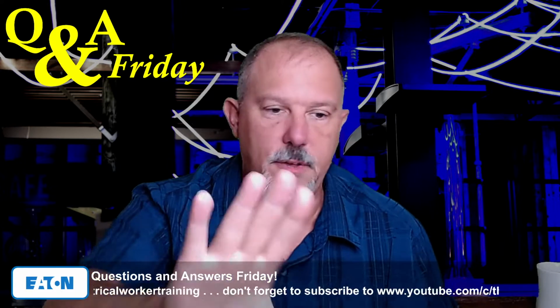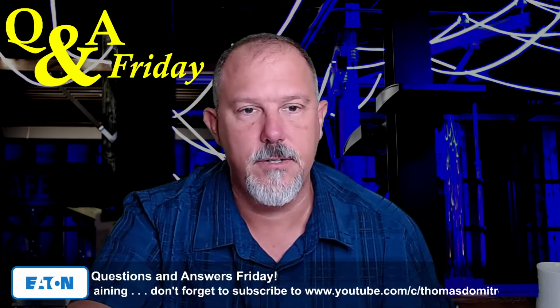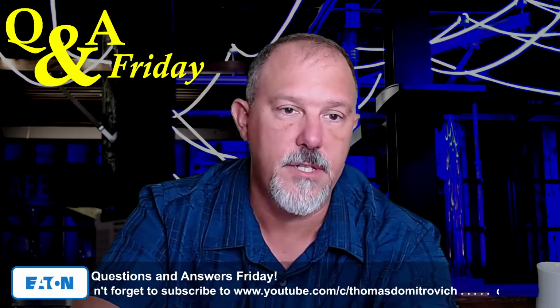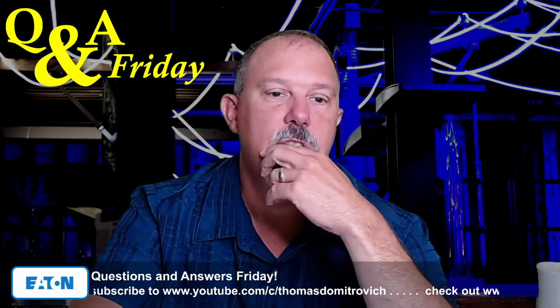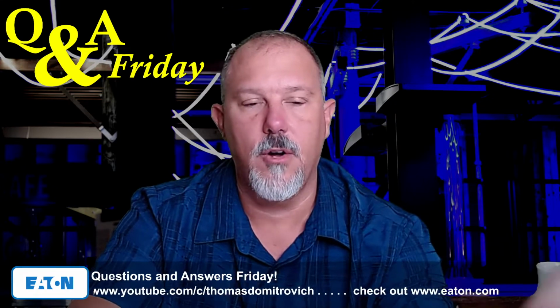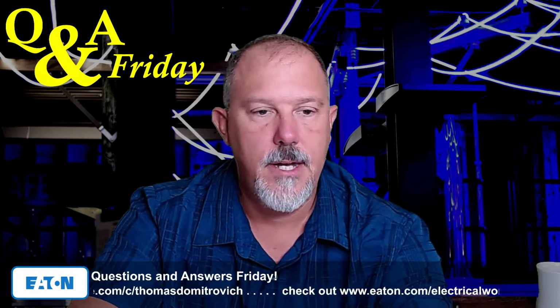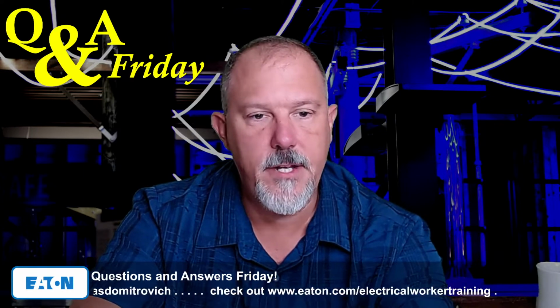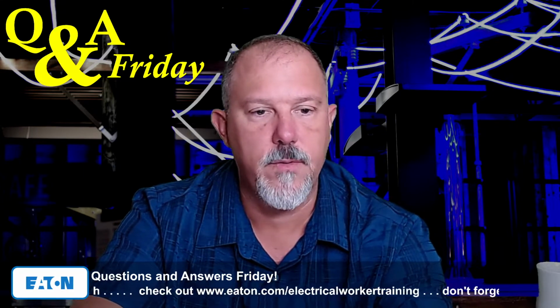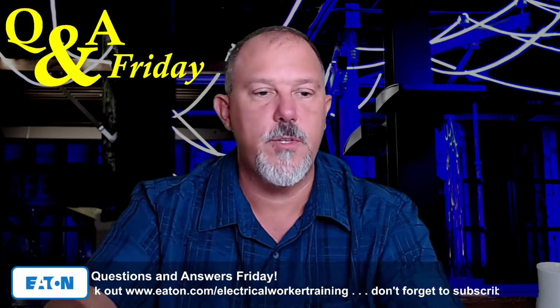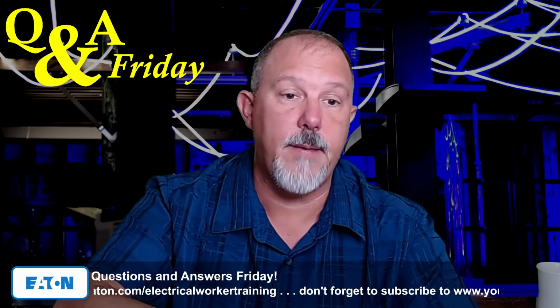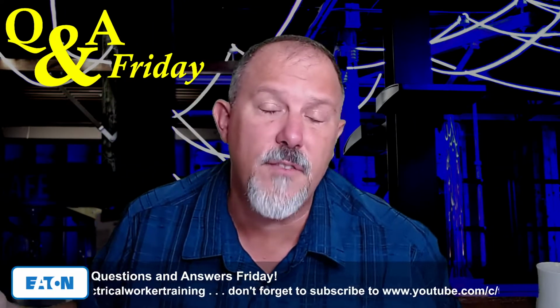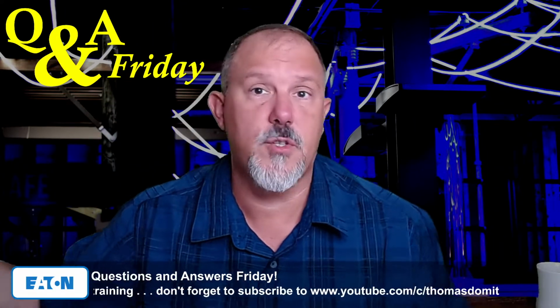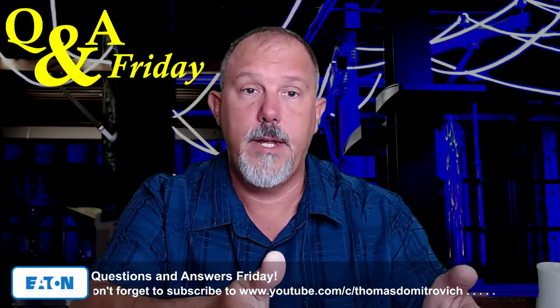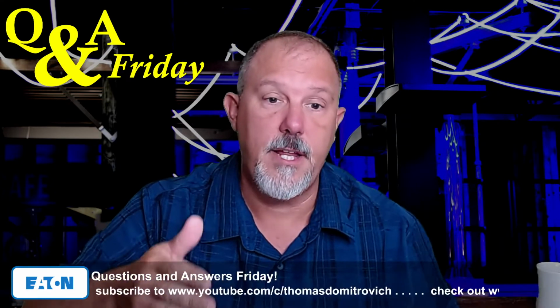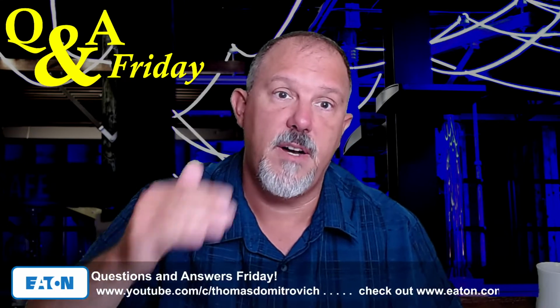And I know you have a lot of dialogue here, and you probably bring up the use of higher resistance conductor terminations as they age. So your point is that the arcing currents are probably going to change. And then you made a statement here about the main breakers, people using the six-switch rule to keep the disconnects or breakers under 1200 amps. Absolutely. They do that now for ground fault. People don't want to put ground fault on 1000 amps and above. So what do they do? 600 amps, right? They'll split that service specifically to get out of the 1000 amps and above requirement to put GFPE.